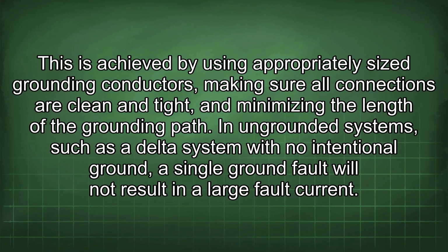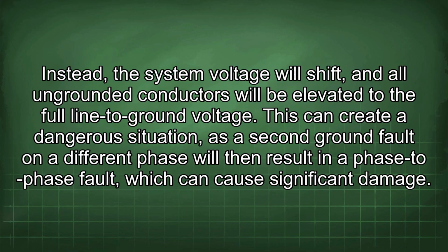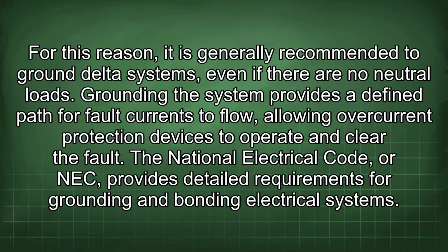In ungrounded systems, such as a delta system with no intentional ground, a single ground fault will not result in a large fault current. Instead, the system voltage will shift, and all ungrounded conductors will be elevated to the full line to ground voltage. This can create a dangerous situation, as a second ground fault on a different phase will then result in a phase-to-phase fault, which can cause significant damage. For this reason, it is generally recommended to ground delta systems, even if there are no neutral loads. Grounding the system provides a defined path for fault currents to flow, allowing overcurrent protection devices to operate and clear the fault.